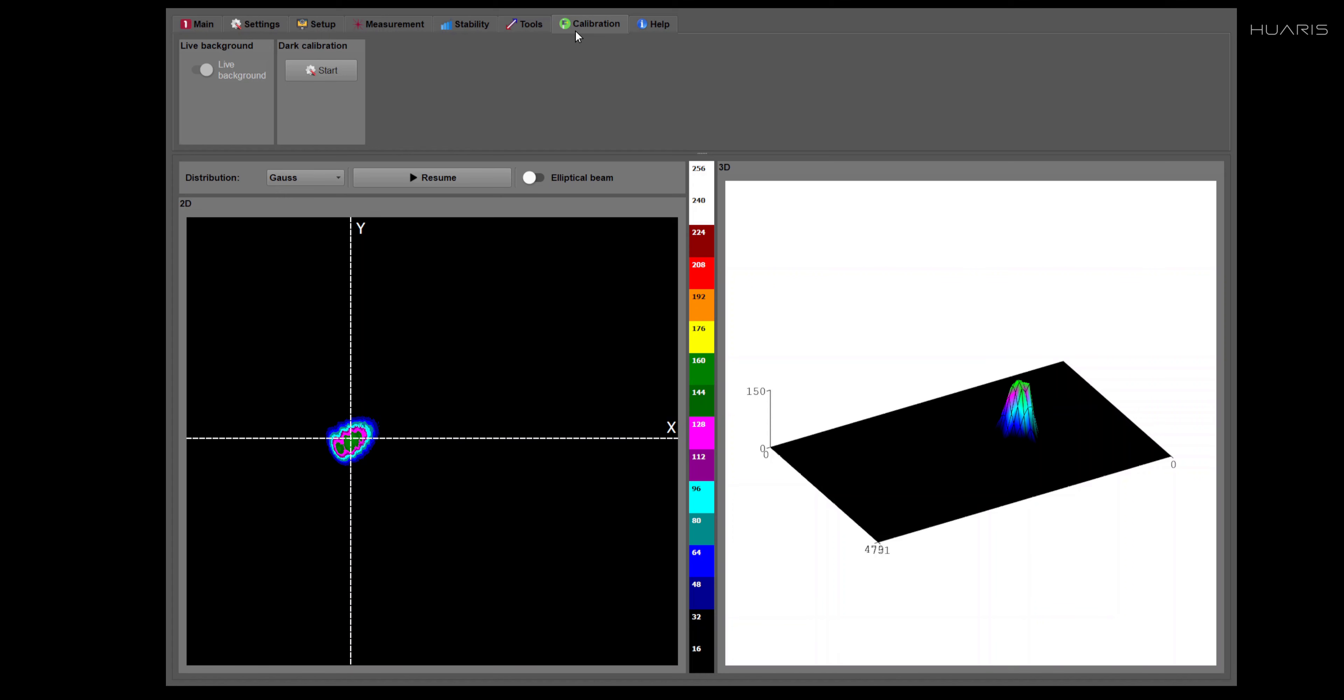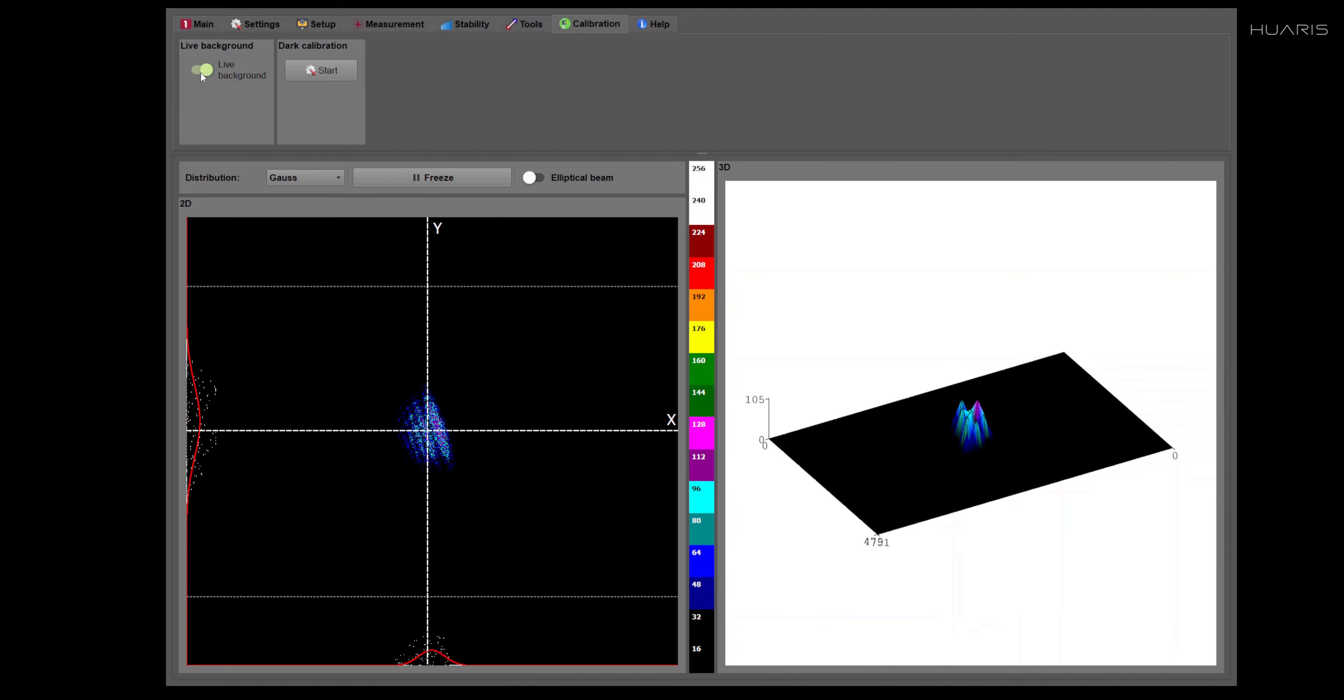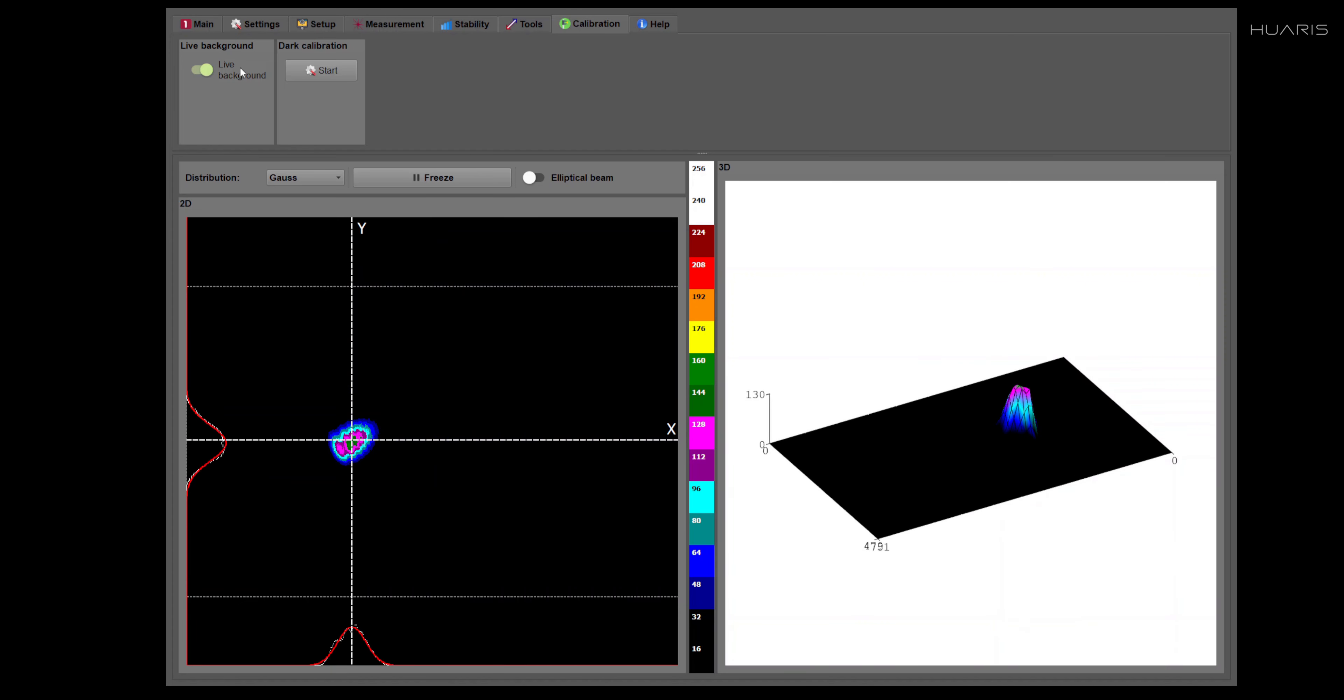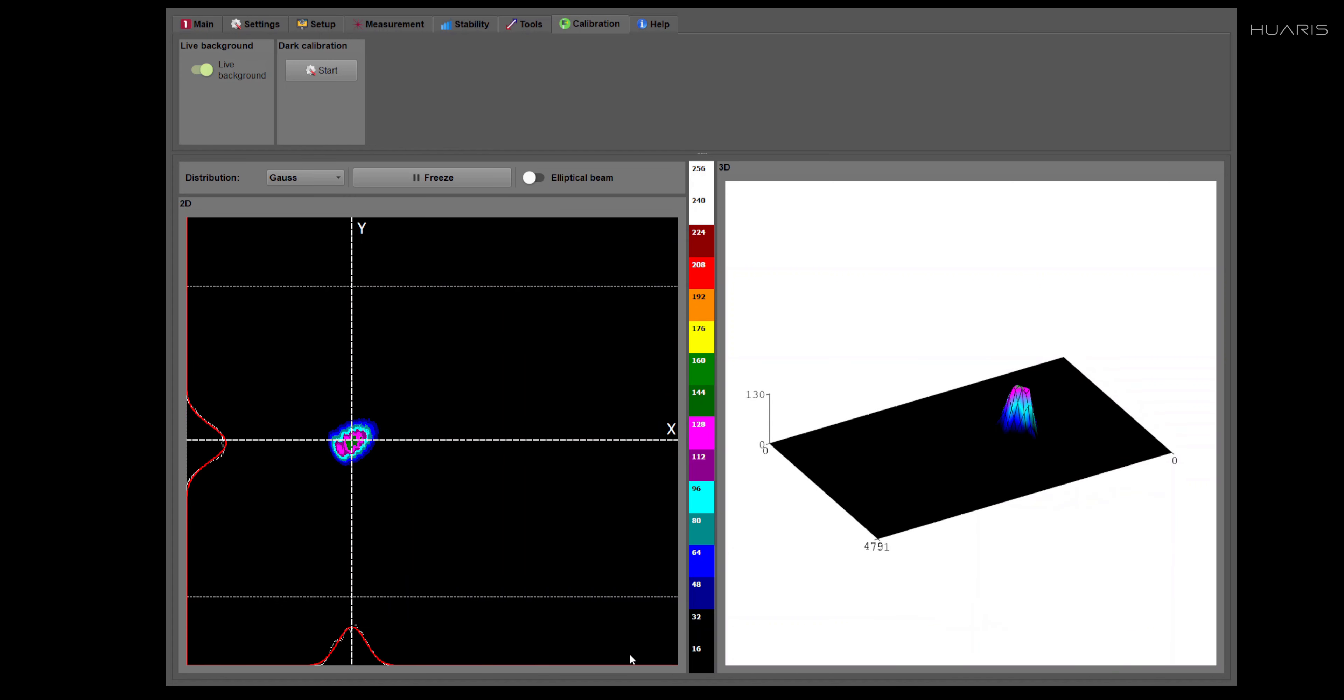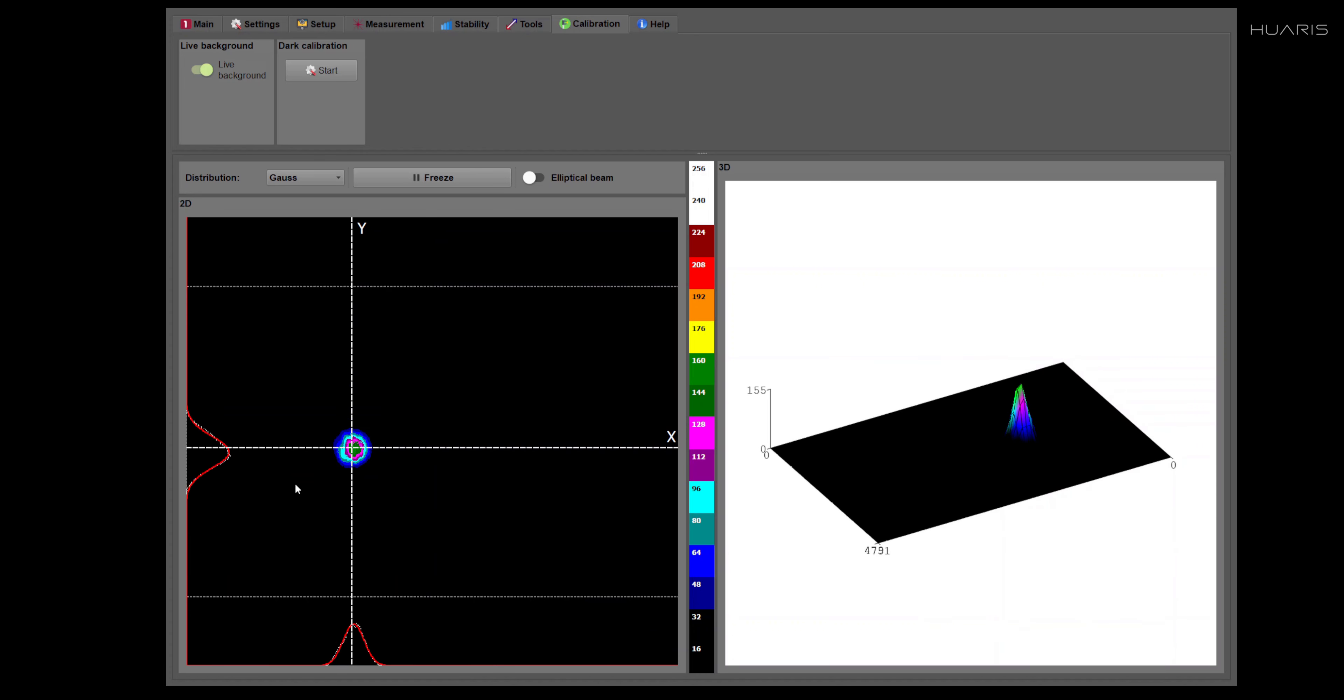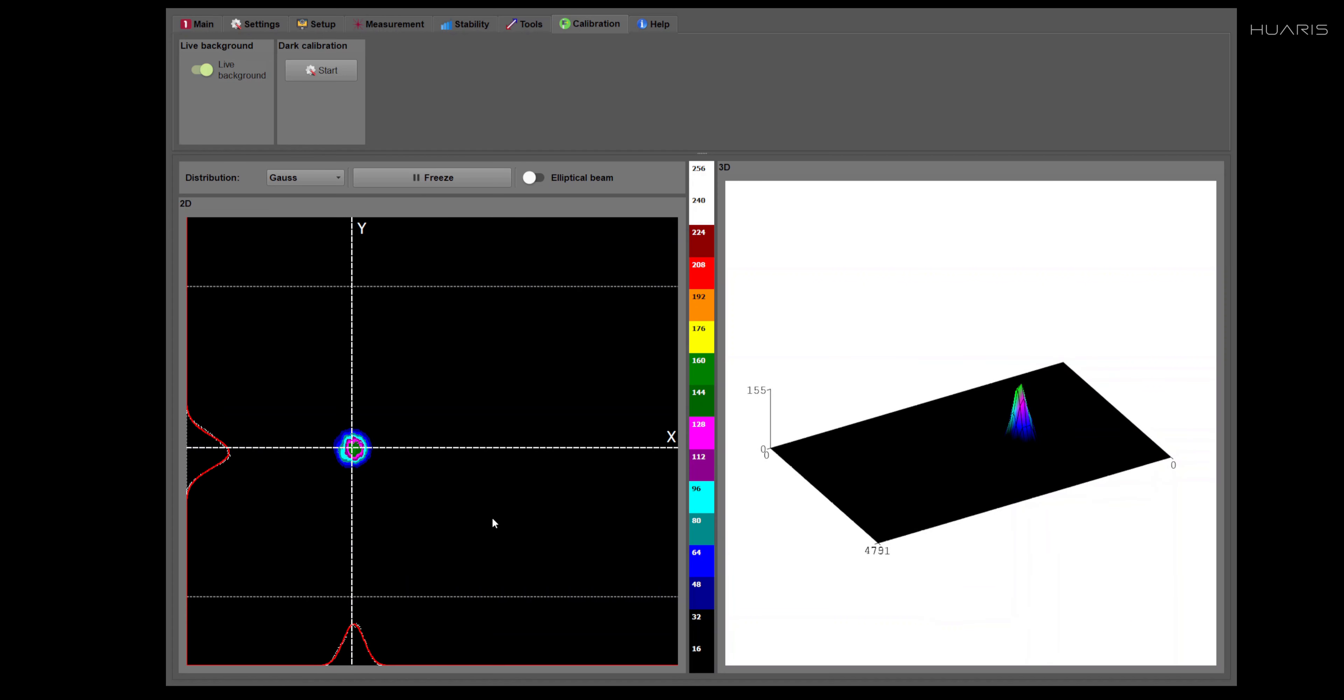Calibration tab is related to basically correcting the noise and ambient lighting. The first option is live background. Live background is devoted to situations where, for example, ambient illumination influences the detector. And it works in a way that basically it checks the level of the light and it makes correction before any calculations are made.